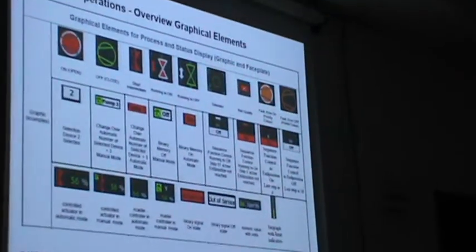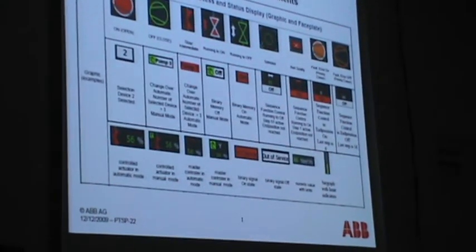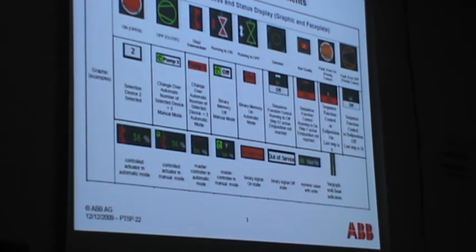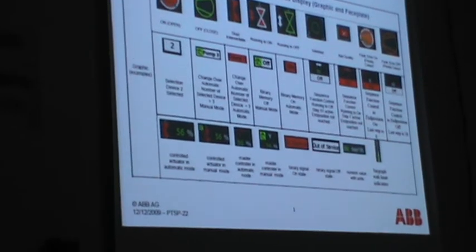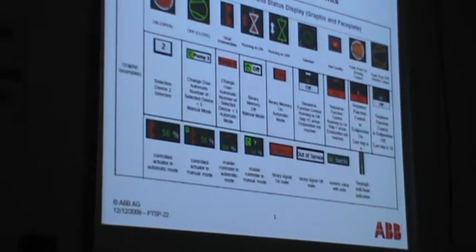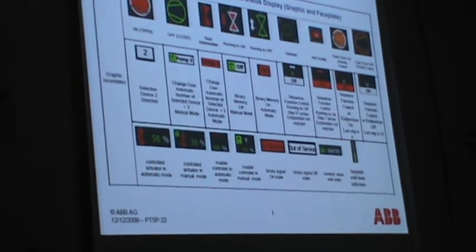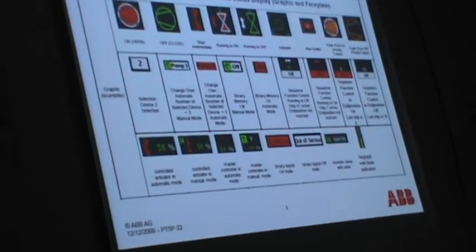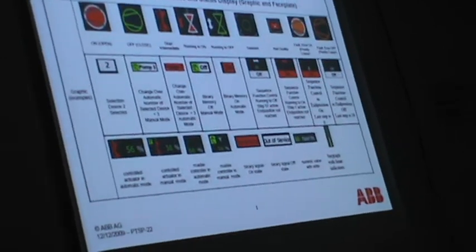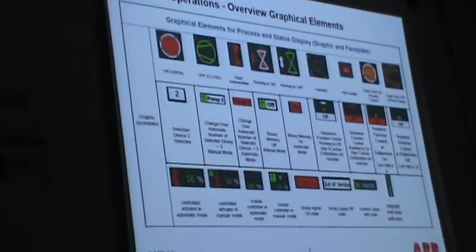Okay. Here we have a separate indication: it will show your command, what percentage you entered, and it will show the feedback also. So this is not from two different things. No separate actuator, no separate controller. It is the same, only a 2-core Profibus cable. This 2-core cable will get the actuator signals and also set the command. So that is the use of Profibus.